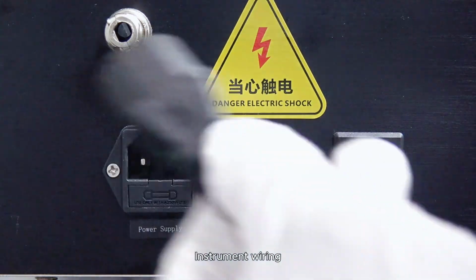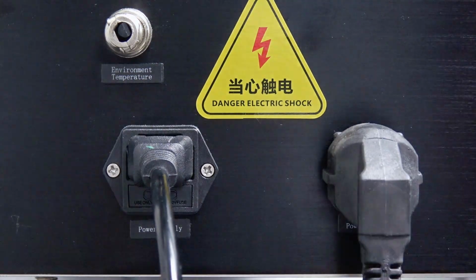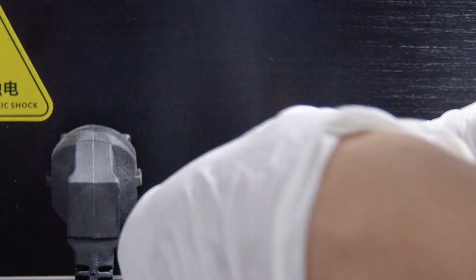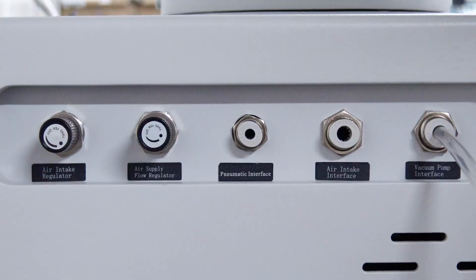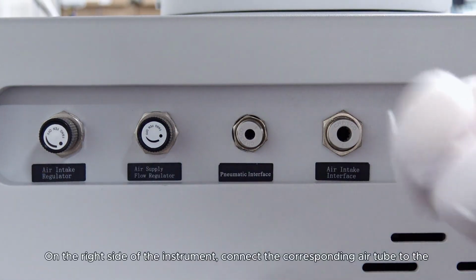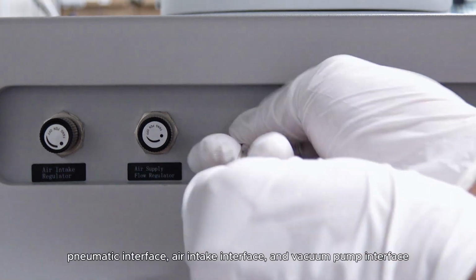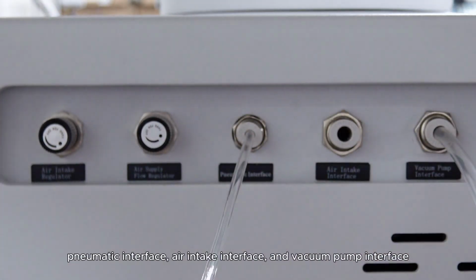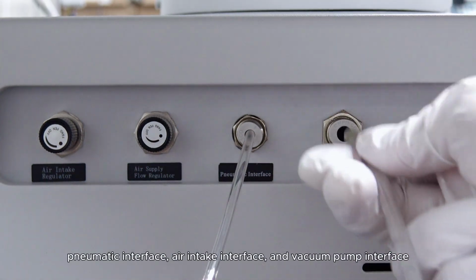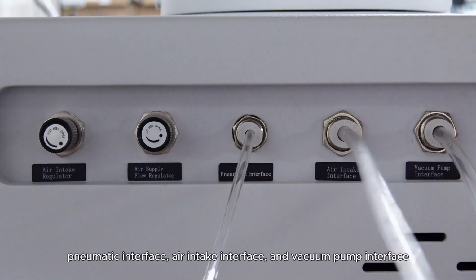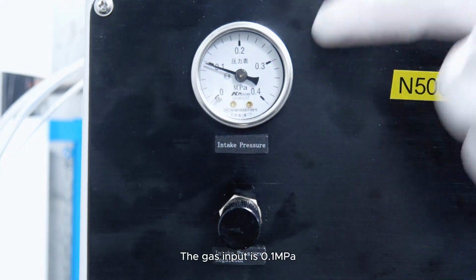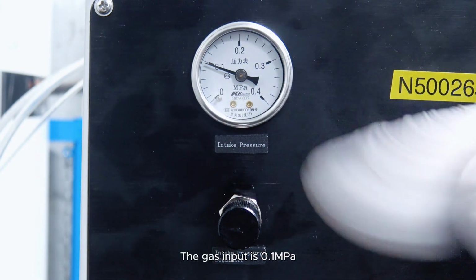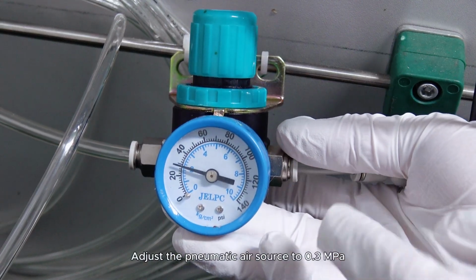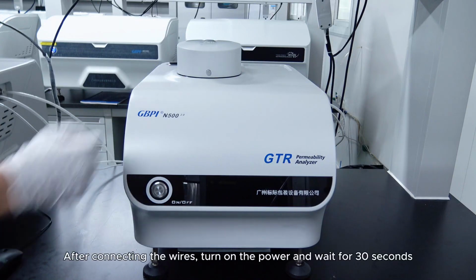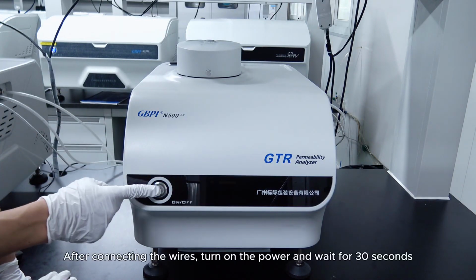Instrument wiring. On the right side of the instrument, connect the corresponding air tube to the pneumatic interface, air intake interface, and vacuum pump interface. The gas input is 0.1 megapascal. Adjust the pneumatic air source to 0.3 megapascal. After connecting the wires, turn on the power and wait for 30 seconds.